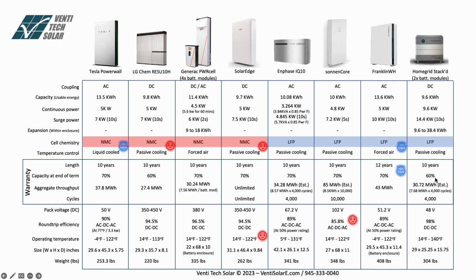I can justify the 60% on the HomeGrid because of how they're pushing the boundaries of the cell. They're allowing the cell to be continuously discharged at 9.6 kilowatts, which will take 1 hour to discharge this pack of 2 modules. 14.4 kilowatts for 10 seconds is also high, and the operating range of 14 degrees Fahrenheit to 140 is also high. Especially with passive cooling, I would think that these cells under these conditions will have 60% capacity after 10 years.